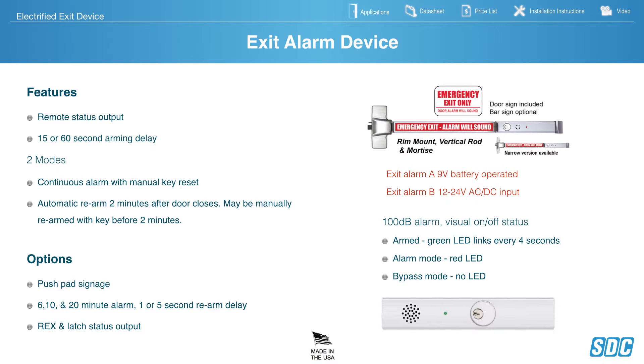SDC Exit Alarm Device — 15 or 60 second arming delay, two modes: Continuous Alarm with Manual Key Reset, or Automatic Rearm 2 minutes after the door closes. May be manually rearmed with key before 2 minutes. Options include Push Pad Signage, 6, 10, and 20-minute alarm, and 1 or 5-second rearm delay, REX and LATCH status outputs.